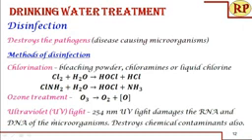What is a major advantage of ultraviolet compared to even chlorination? Chlorination, actually, if you have organic impurities, it actually forms some carcinogenic byproducts, which is not good for health. And there is still a debate going on, especially by the environmentalists who don't want chlorination to be adopted as a disinfection method. But still, we try to eliminate those carcinogenic byproducts, and we still adopt chlorination widely because it's very cheap and can be very easily adopted for large volumes of water.